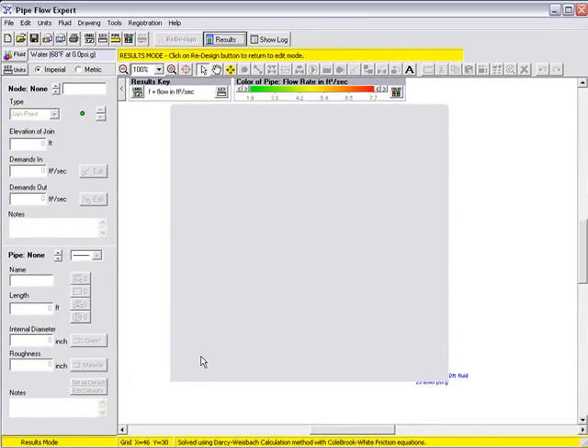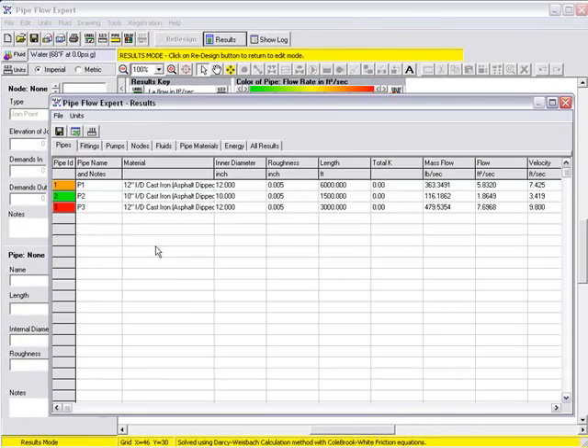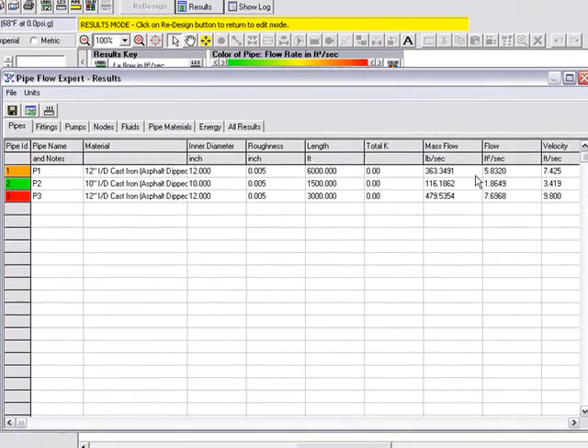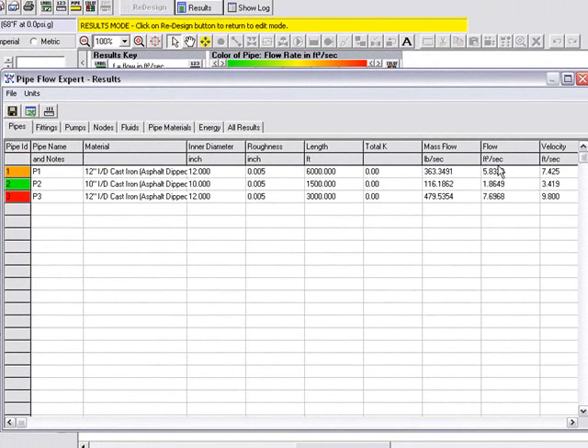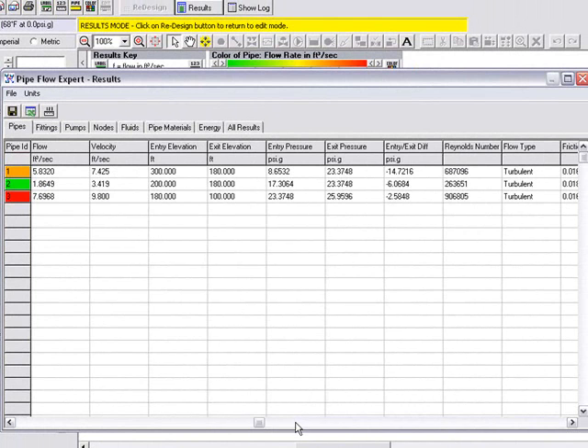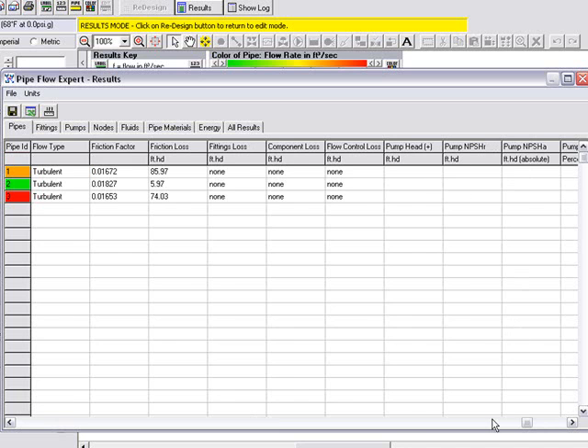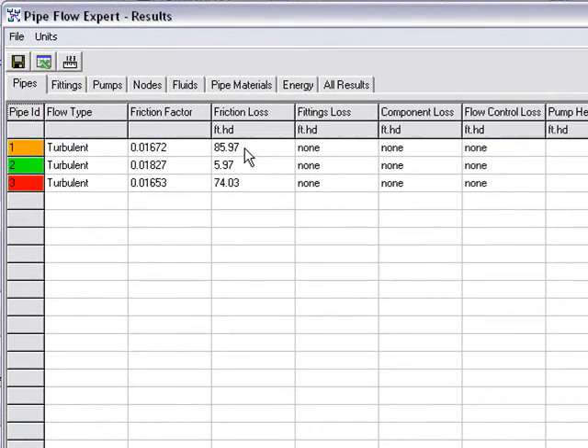If we select yes we are now shown a spreadsheet like table which gives us—we are on the pipes tab which gives us the information about the pipes that we entered. As we move across the grid we can now see the flow that has been calculated that will occur in each pipe and the velocity in each pipe. If we scroll to the right we can see the entry elevation of each pipe, the exit elevation, the entry pressure, the exit pressure, the difference in pressure between the start and the end of the pipe and some further information such as the Reynolds number, the flow type in the pipe, the friction factor and the friction loss in that particular pipe.